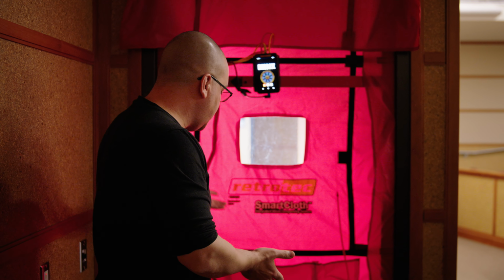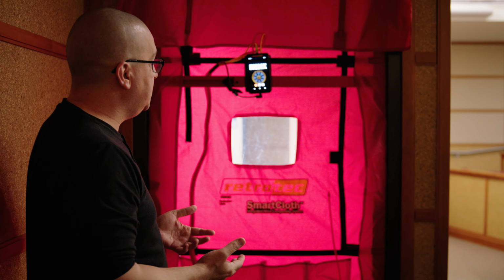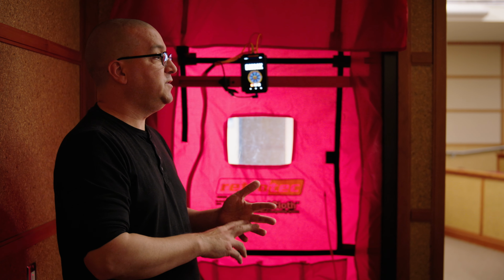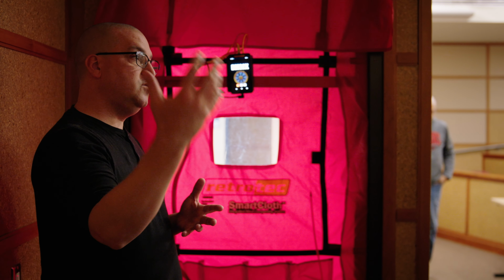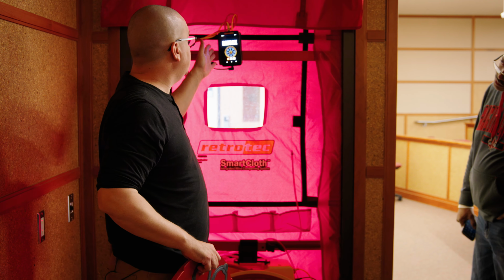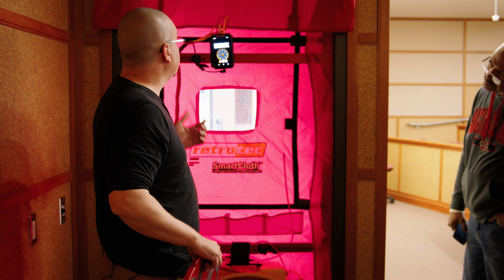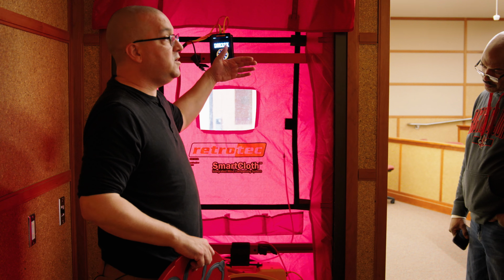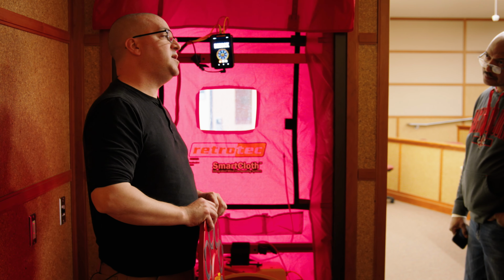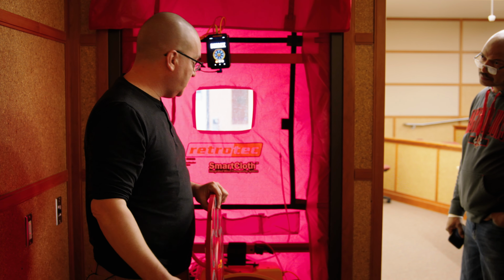This is a blower door setup here. Basically it's a temporary door frame with a fan in it, and that measures the air leakage of the house. The blower door gives you the cubic feet per minute number, the CFM number, and if you have that, you can calculate air changes per hour. On the gauge, our manometer, if it's a super leaky 1850s farmhouse that can only get to like 30 pascals instead of 50, the computer will extrapolate and say, best guess, this is what it probably would be if we could get it to negative 50 pascals.